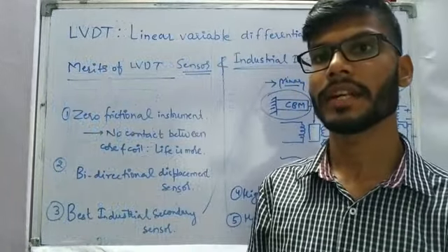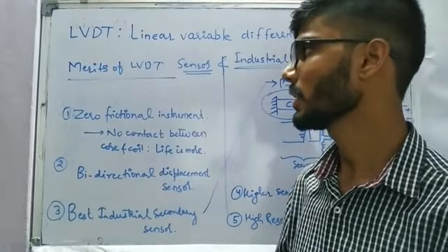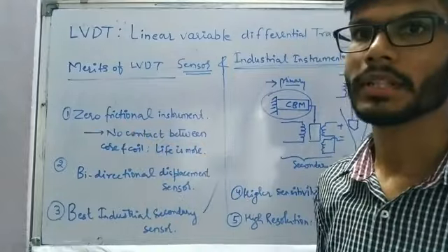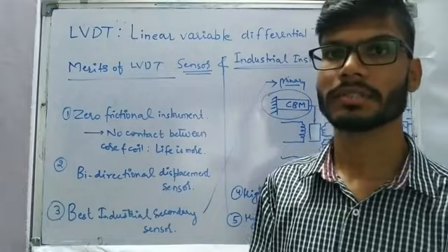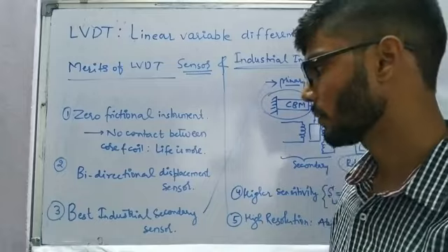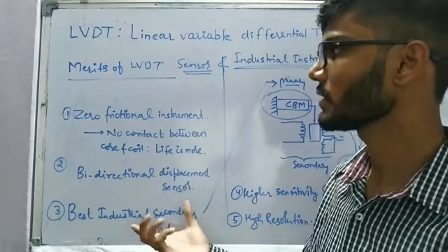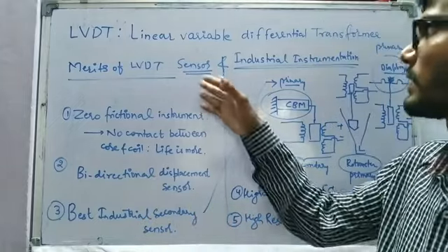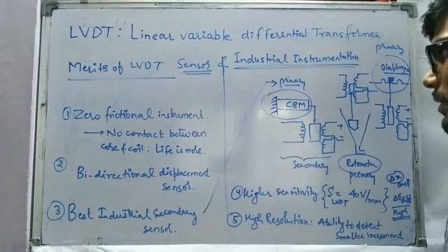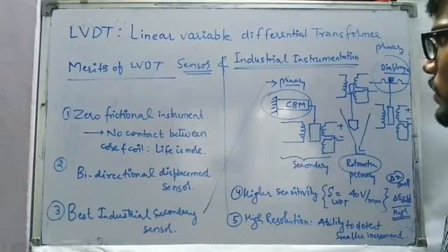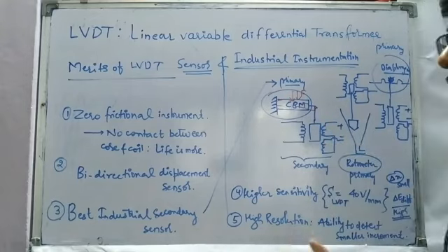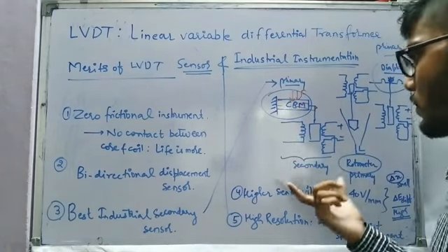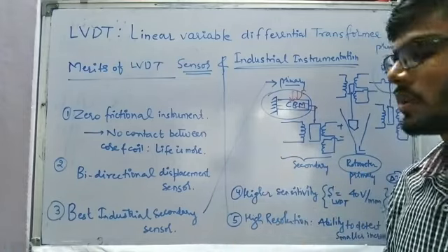Understanding the working principle and construction of LVDT, we can discuss its merits. First, it is a zero-friction instrument because there is no contact between the core and the coil, so its lifetime is longer. Second, it is a bi-directional displacement sensor because it can detect both negative and positive displacement with respect to the null point. It is also used as an industrial secondary sensor. For example, the core of LVDT can be connected to a cantilever beam — if force is applied and the beam deflects downward, the core displaces accordingly, and the secondary sensor gives output proportional to the applied force.